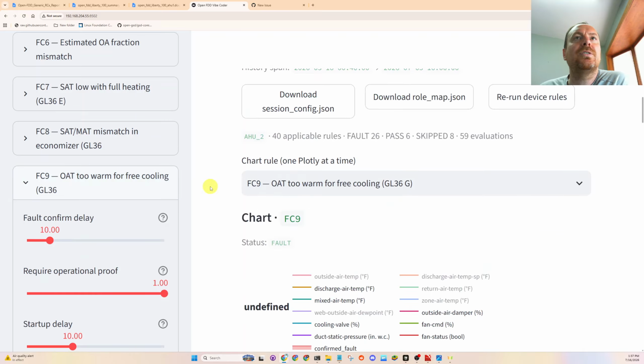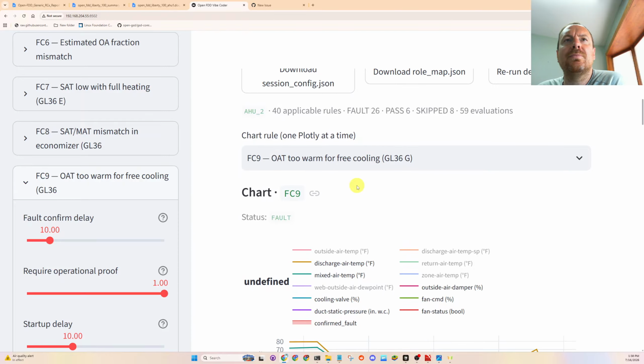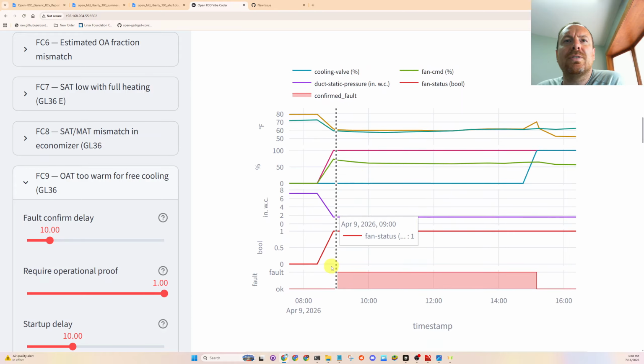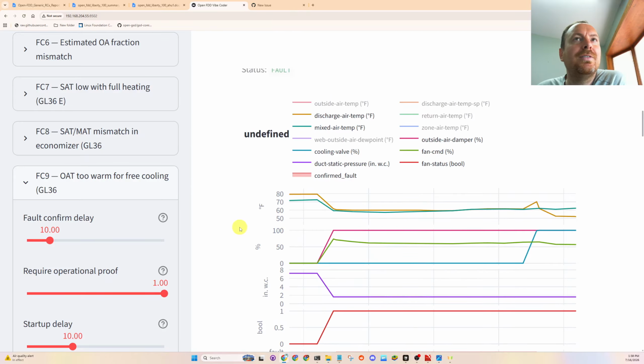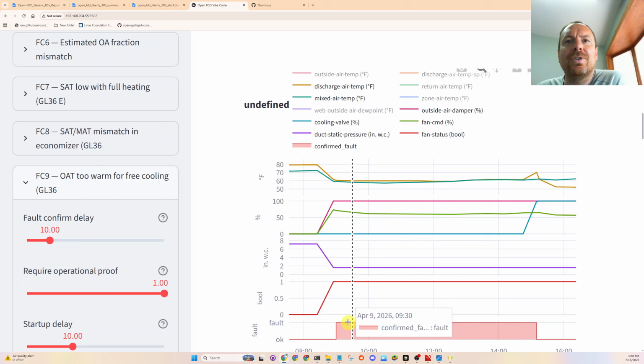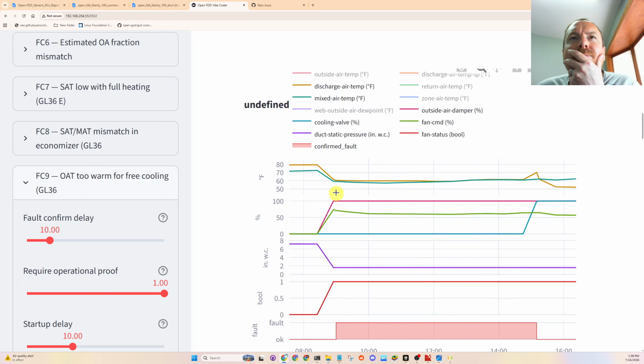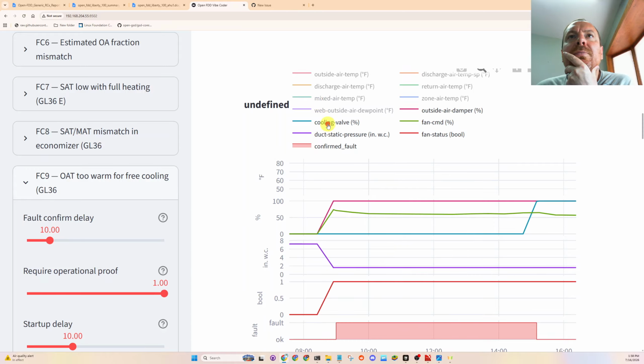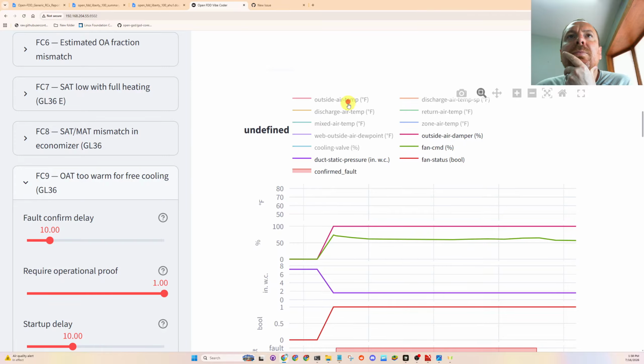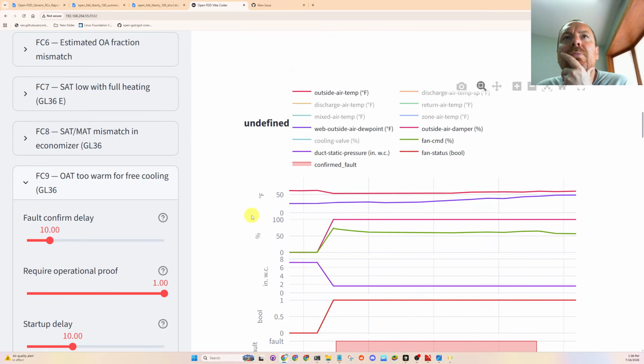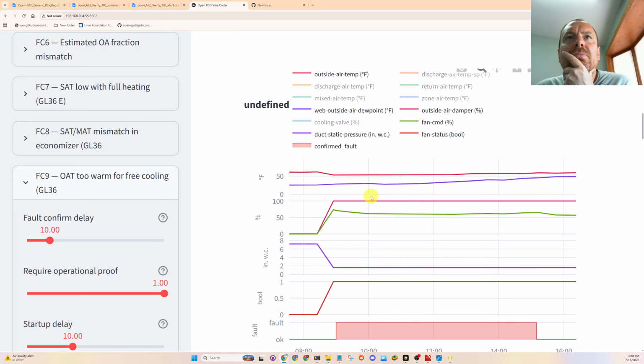Let's look at this guy. Let's look at fault condition. Oh, that was fault condition 9: outside air temperature too warm for free cooling. Oh, that's what this was. Sorry, I was looking at the wrong fault. Outside air temperature too warm for free cooling. Let's look at outdoor air temperature, and then I have dew point on here too. Let's get rid of all this other stuff.